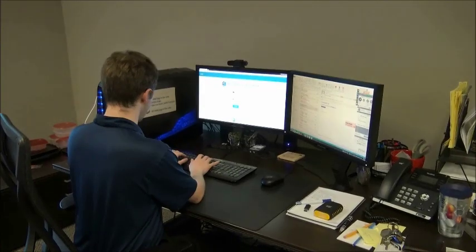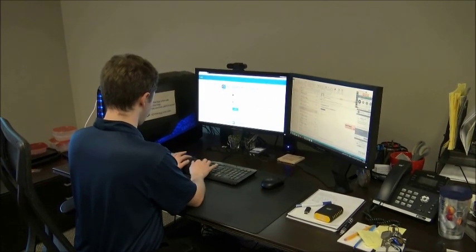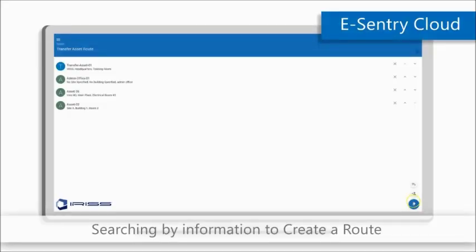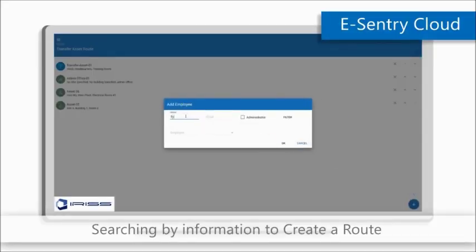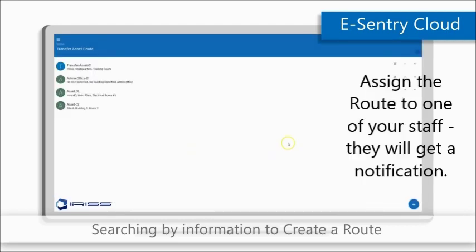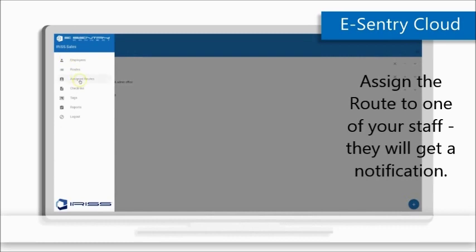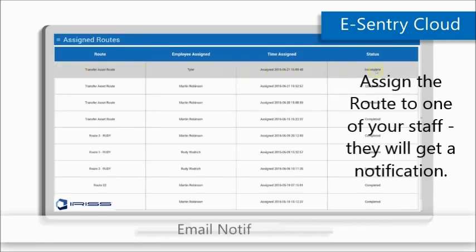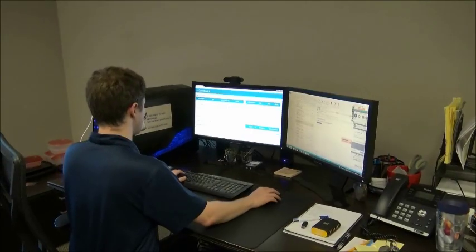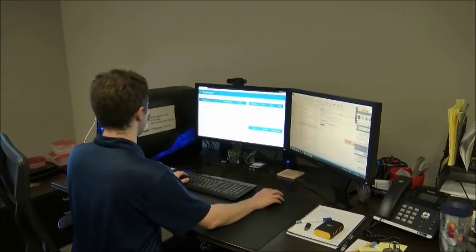Once the route has been created and saved, it can be used repeatedly in the future. We'll assign our electrical ultrasound route to one of our technicians. He will get a notification email, and when he logs into the eSentry app on his smartphone or tablet, he will see the list of assets he needs to go and inspect. Route creation is done and it's time to head out into the plant.